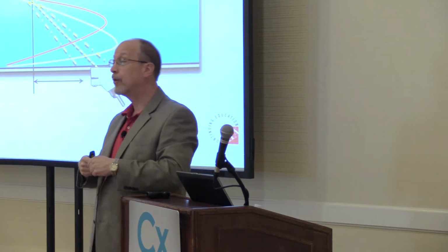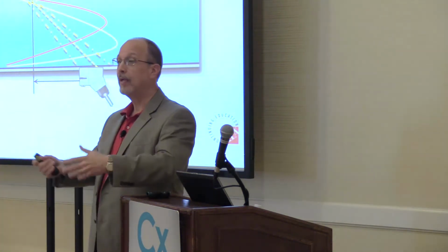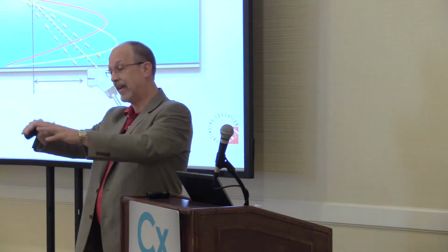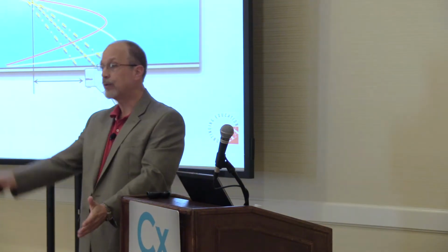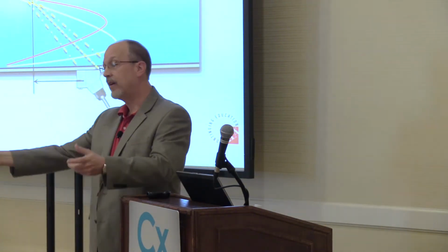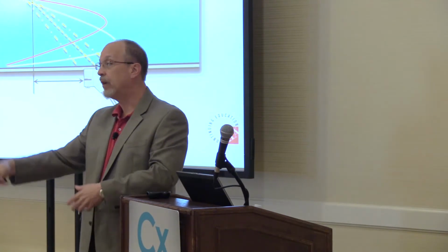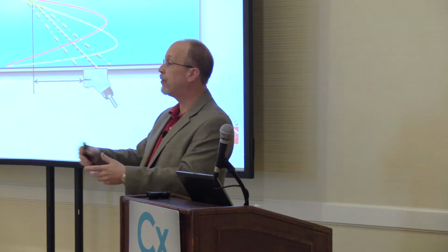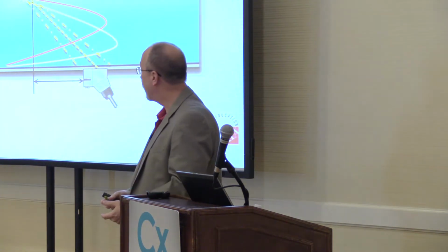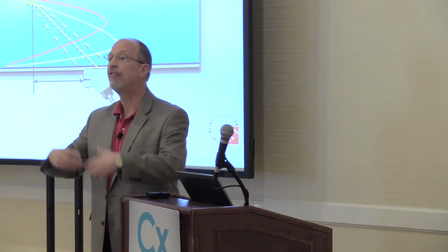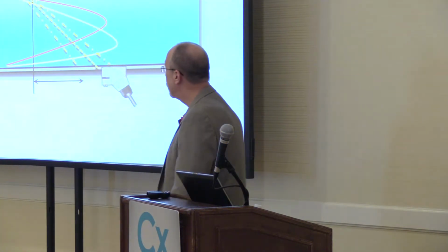You ever go see a big HDPE piping? It's a 36-inch pipe laying on the ground, it's like an egg. It's not even round. So the math that we use is based upon a perfect symmetrical circle. We don't have that. So if you have to move the transducer, and you get it to read, very likely it's better than 5%. If you start to go farther apart and it faults, you're not going to pick up an inaccuracy. You're not likely to ever get a transit time flow meter that's 10 or 20% off because it won't read. It'll fault. So that's the salvation of a transit time meter. If you're too far out of the spectrum, it won't work.